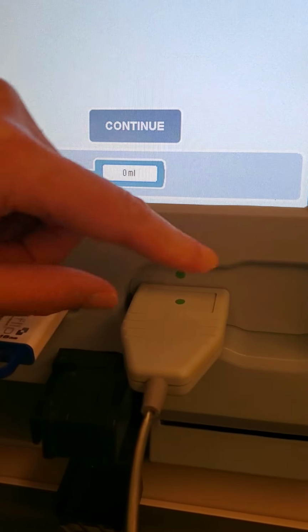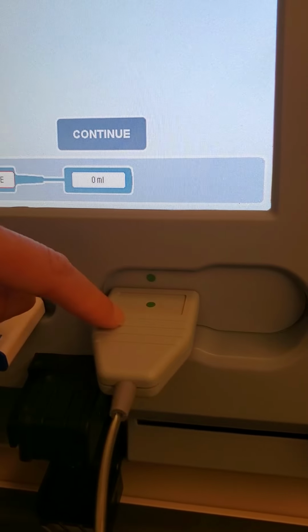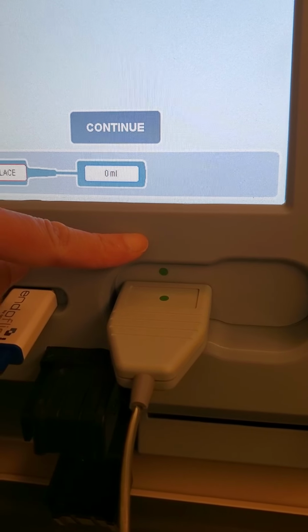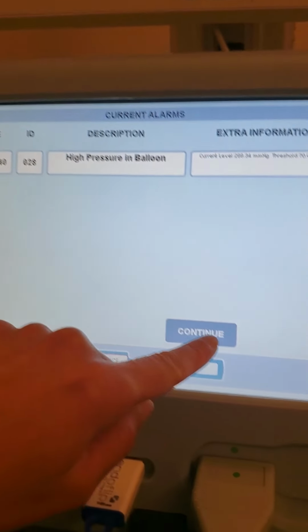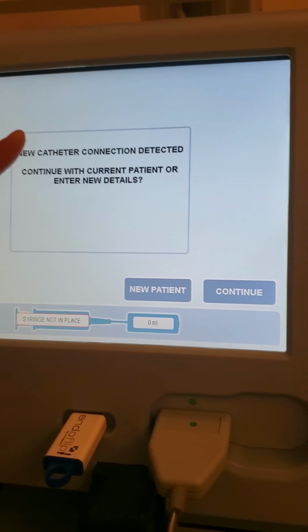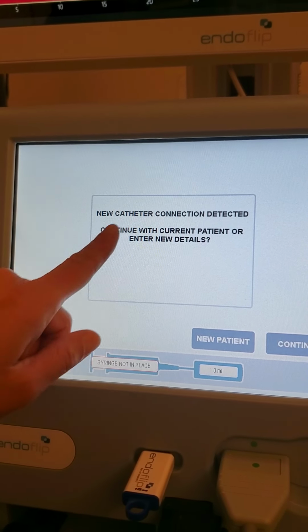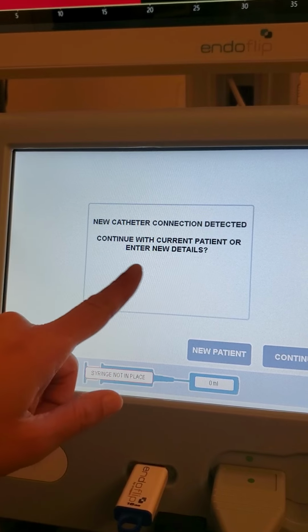We want to plug it in when it's still wet. It seems counterintuitive, but we want to plug it in when it's still wet because it helps the machine read the card, and the card tells the machine what size balloon you just plugged in. If you get this high pressure alert, just press continue to bypass it. Now it'll say new catheter detected. Do you want to continue with the current patient or enter new details?